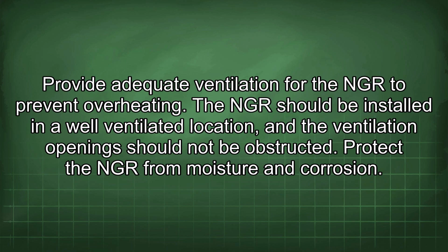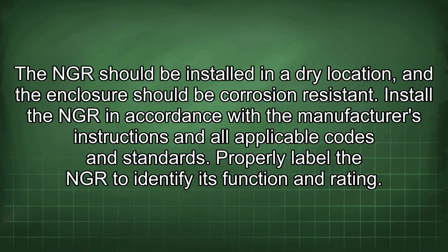Provide adequate ventilation for the NGR to prevent overheating. The NGR should be installed in a well-ventilated location, and the ventilation openings should not be obstructed. Protect the NGR from moisture and corrosion. The NGR should be installed in a dry location, and the enclosure should be corrosion resistant. Install the NGR in accordance with the manufacturer's instructions and all applicable codes and standards.